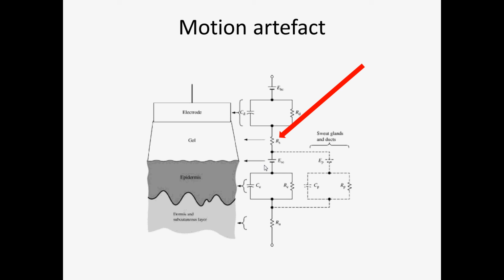And this was because that specific volunteer had a small artery going under the skin of his scalp, right under the electrode. That was making the electrode bump away from the skin, obviously not something you can actually observe, but that was happening, and I had this bumping in the EEG, exactly in rhythm with the heart.